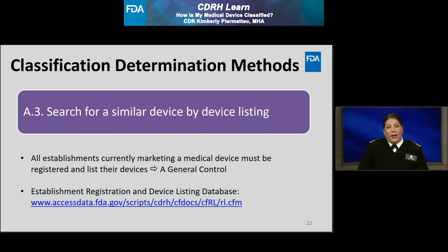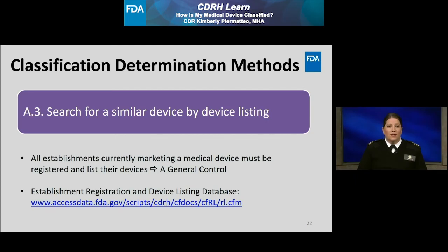The third method I recommend is to search for a similar device by device listing. This method is useful when determining how a currently marketed device is classified, because establishment registration and device listing are a general control — meaning all medical device establishments currently marketing a device in the United States must be registered with FDA and list their devices. So if you know of a similar device currently being marketed, you can search for it by its listing and see if the same product classification applies to your device.